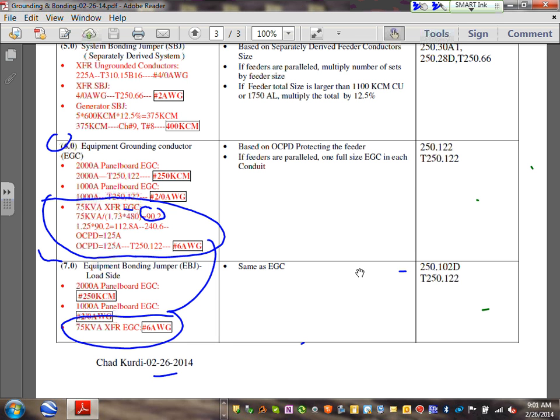Any comments, any questions? So the equipment bonding jumper on the load side and the equipment grounding conductor are identical. None of you will understand it without looking at the diagram. You have to look at where the conductors are coming from, and you have to use the same naming, because that's what the code uses to name these things.